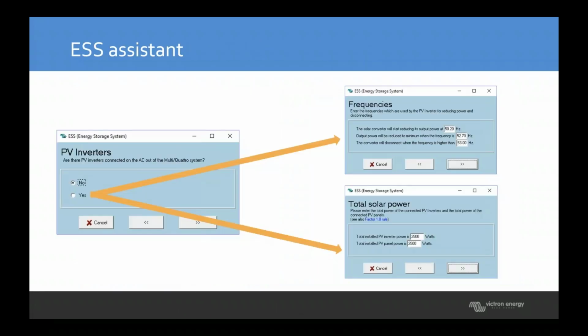Within that assistant, which is kind of like a wizard that you click through, you'll select whether you have a PV inverter connected. If you do, you click yes, and it'll ask you some questions based upon the sizing. So the frequency range you leave by default if you're using a Fronius system, and for the total solar power system, make sure that you're following that 1-to-1 rule. So you need to enter how many PV panels you've got and how big the PV inverter is.